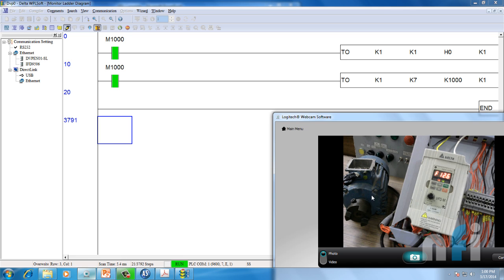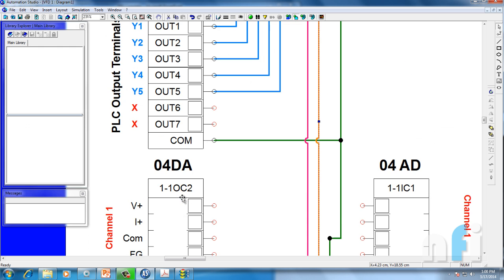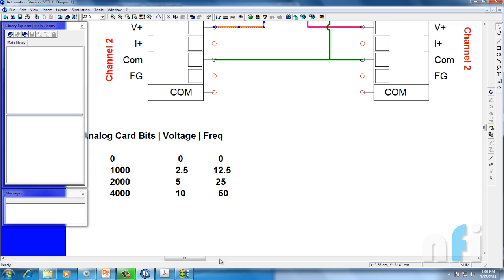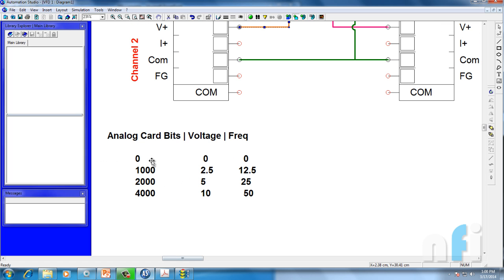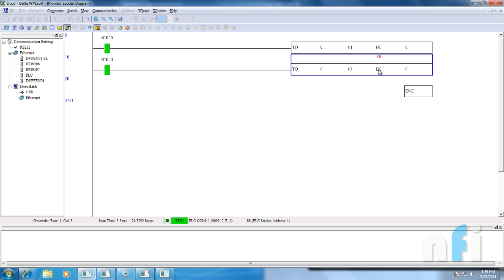The frequency changed to 12.6 Hz because a value of 1000 means I'm giving 2.5 volts. To make a note: at 0 bits, voltage is 0 volts and frequency is 0 Hz. At 1000 bits, voltage is 2.5 volts and frequency is 12.5 Hz. At 4000 bits, voltage is 10 volts and frequency is 50 Hz.